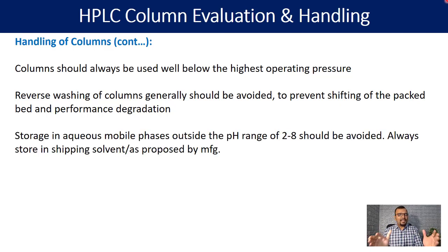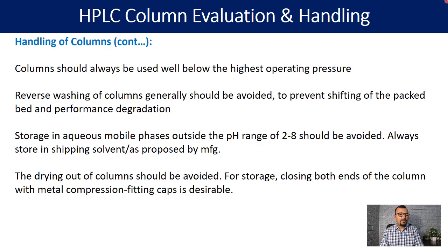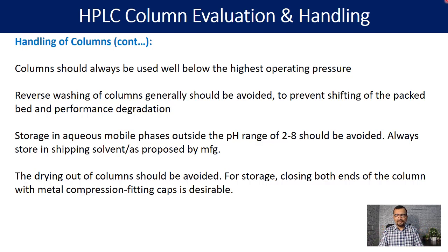Storage in aqueous mobile phases outside the pH range of 2 to 8 should be avoided. Always store the column in the shipping solvent or as proposed by the manufacturer. The drying out of the column should be avoided. For storage, always use the end cap so that the column will not get dry. These are all the key points on how to determine your column performance and how to maintain the health of the column.